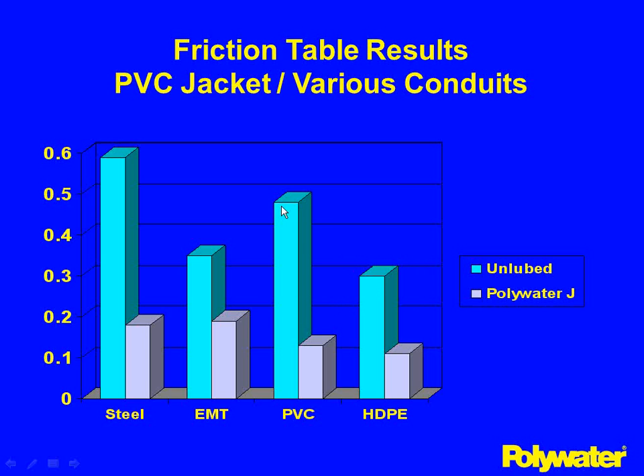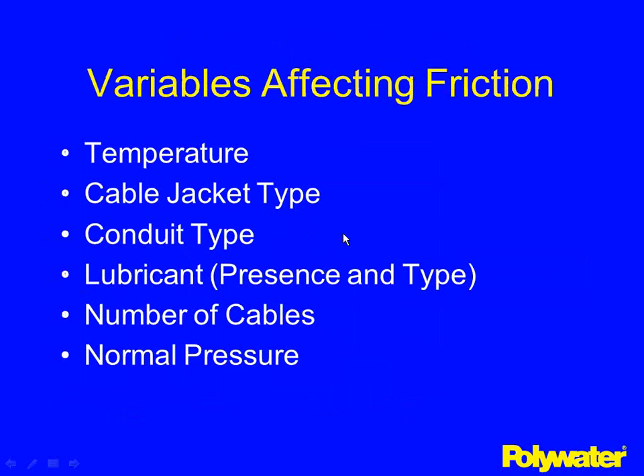Keep in mind that unlubricated values represent crews not using enough cable pulling lubricant. It is very important that you specify Polywater lubricants every time people are pulling cable. If they don't use lubricant, the numbers become much higher — even small differences in coefficients of friction will make big differences in ending tensions.